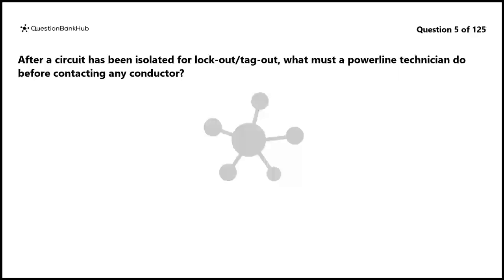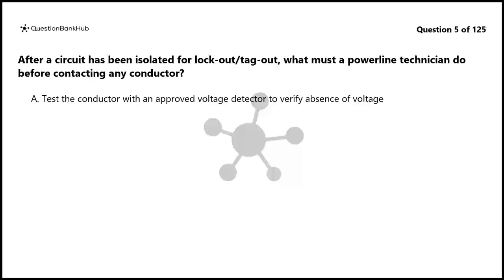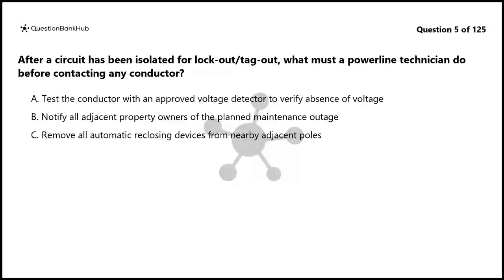Question 5. After a circuit has been isolated for lockout-tagout, what must a Powerline technician do before contacting any conductor? A. Test the conductor with an approved voltage detector to verify absence of voltage. B. Notify all adjacent property owners of the planned maintenance outage. C. Remove all automatic reclosing devices from nearby adjacent poles. D. Install temporary protective grounds at the immediate worksite location.